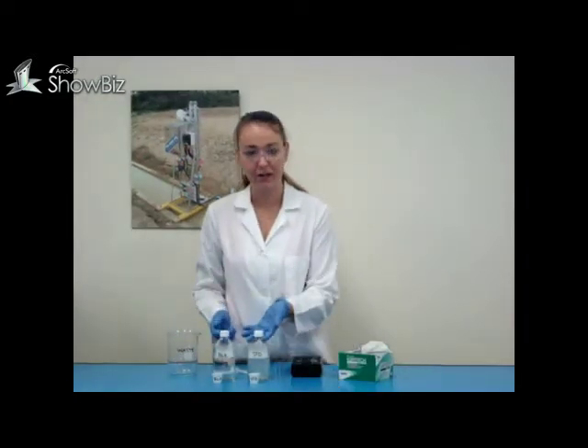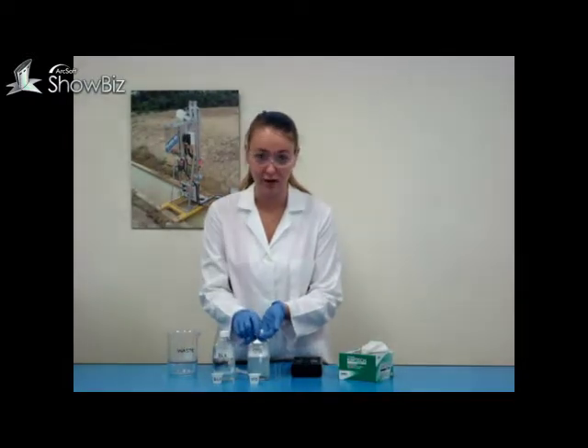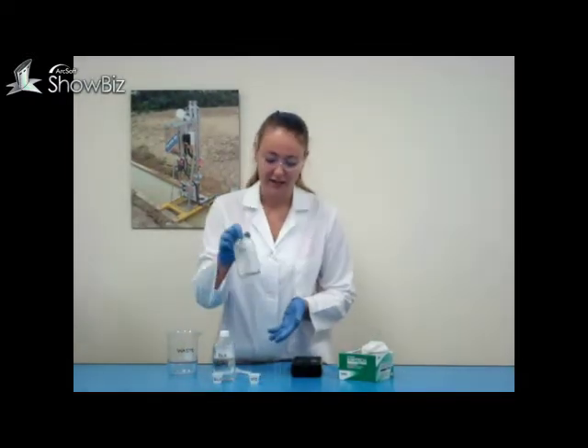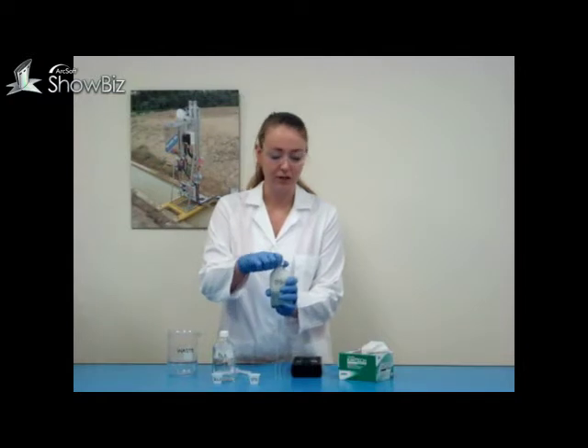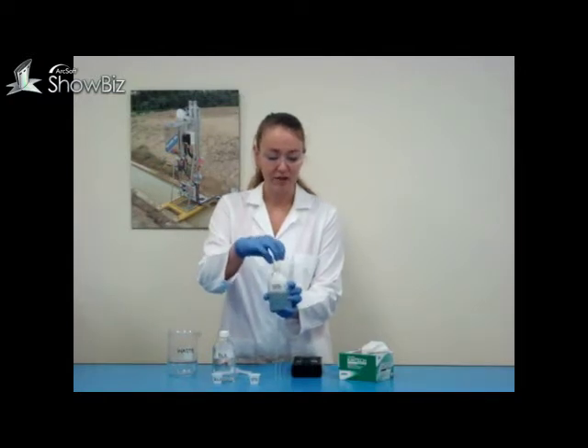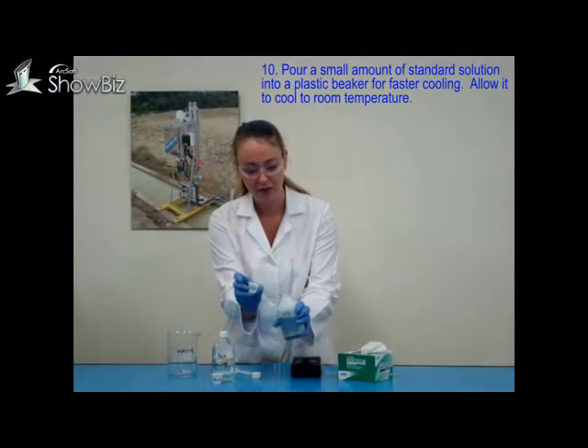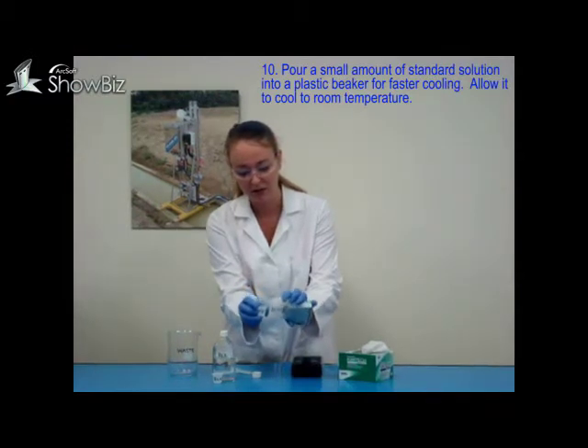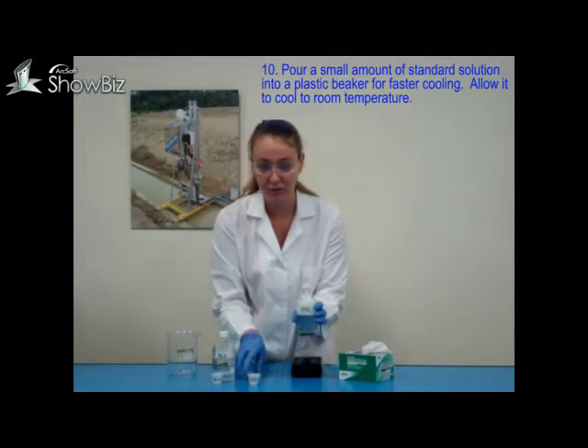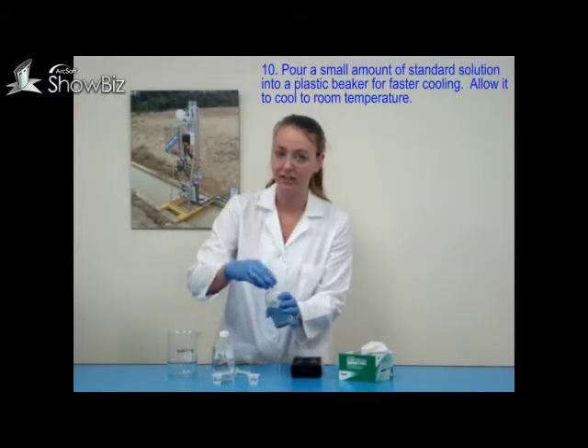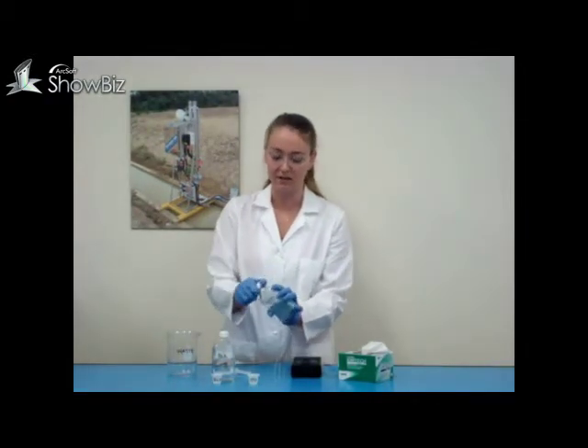Now we just need to wait for our standard solution to reach cloud. Our standard has now reached cloud point, and we need to remove it from the hot water bath so that it cools down to room temperature. To facilitate quicker cooling, pour a small amount of your standard into a small plastic beaker. The solution needs to cool to room temperature so that it can become optically clear so that it can be used in the TD-500D.